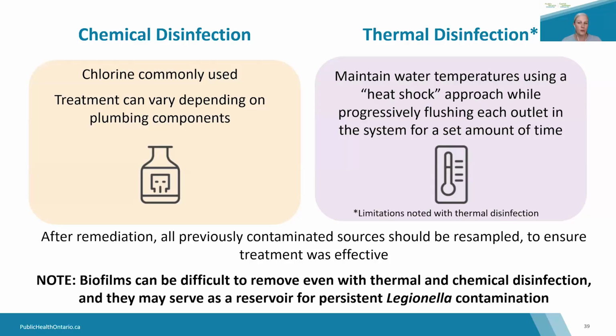There are limitations noted with thermal disinfection. There may be challenges with material compatibility. Distributing adequate hot water at elevated temperatures throughout the system can also be a challenge. And there can be the potential for recolonization of Legionella if nutrients and biofilm cannot be purged. Either method requires significant planning, time, and staffing to ensure that the process is effective and to protect residents from exposure to chemicals or heat. Next slide, please.